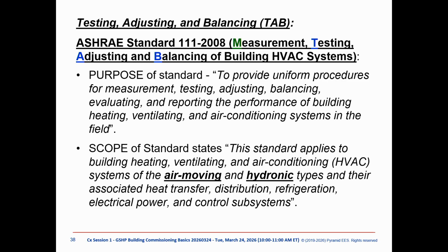But sometimes I have to hear excuses - oh, I couldn't get this. Well, why couldn't you get this? Because the port I needed was not here. So I've been telling customers, please involve the TAB contractor up front for testing, adjusting, and balancing. It applies to both air moving systems and hydronic types. With geothermal heat pump systems, you have hydronic, air, or air and water systems.